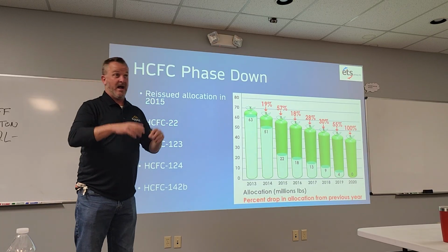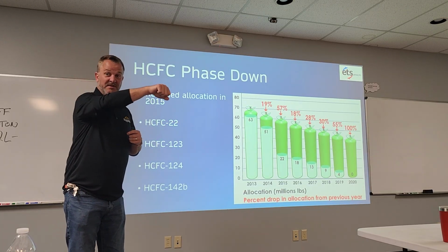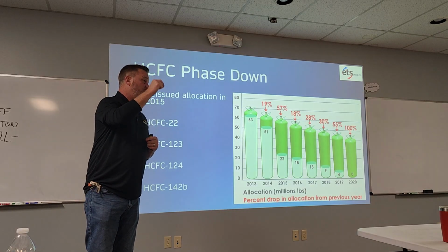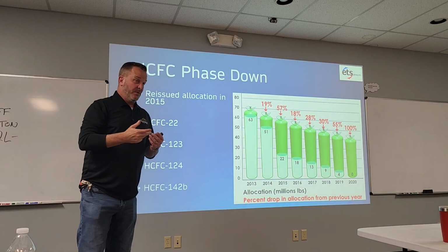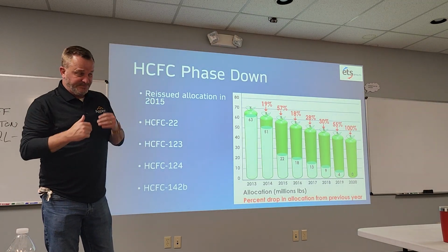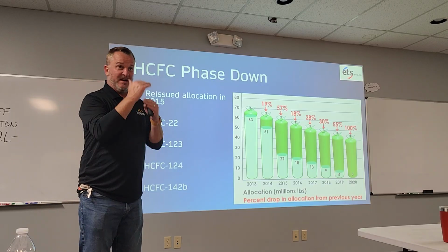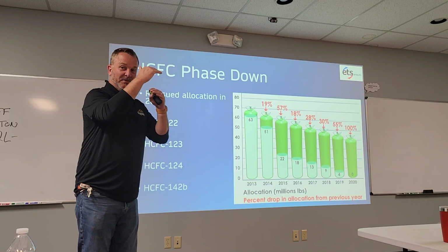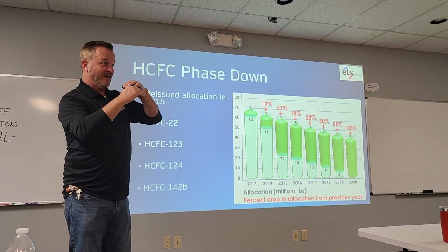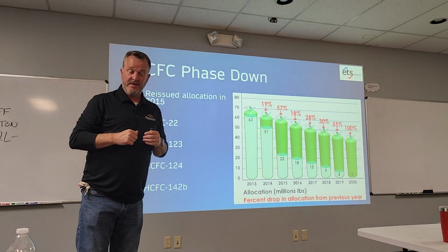Reclaimers have high-end gas chromatographs. They're literally hooking up these cylinders and they can tell you exactly what's in that cylinder. What we'd see a lot of times, and they'll give you those reports, is it's 25% R22, 40% 410A, some 407C in there, and also some 134 in there.